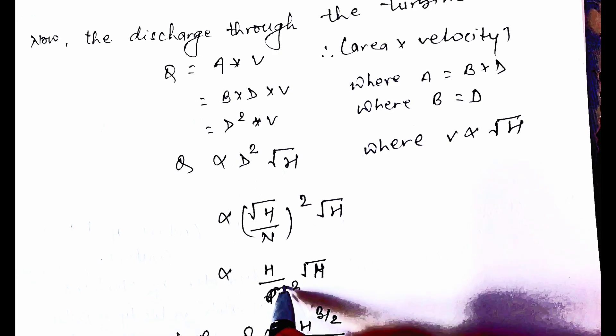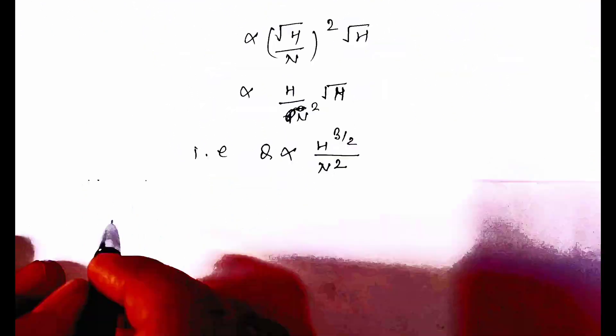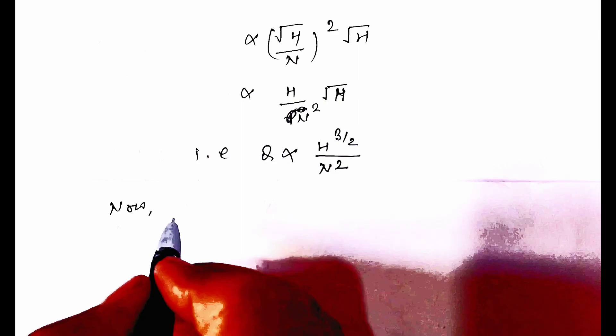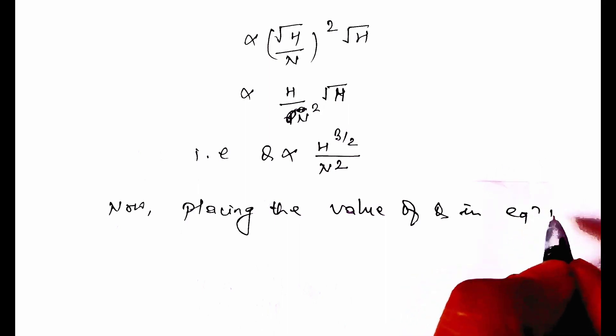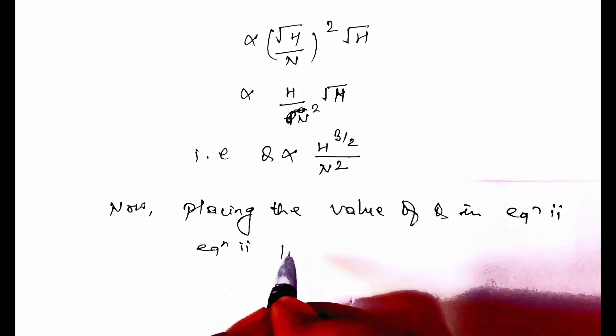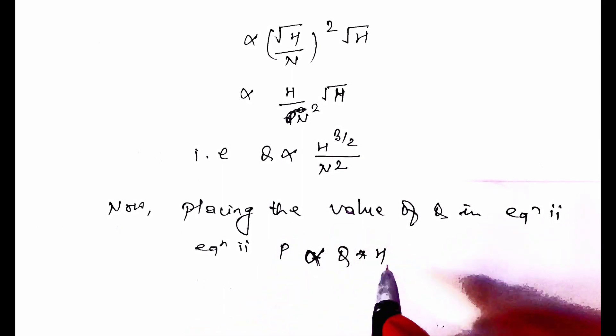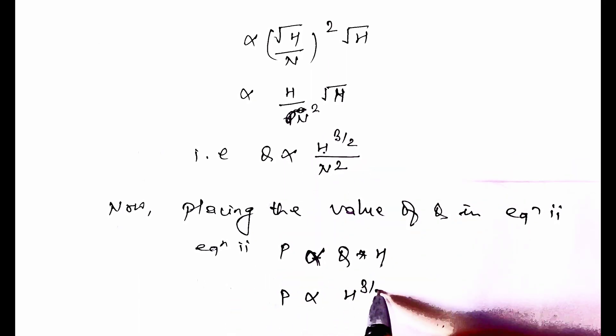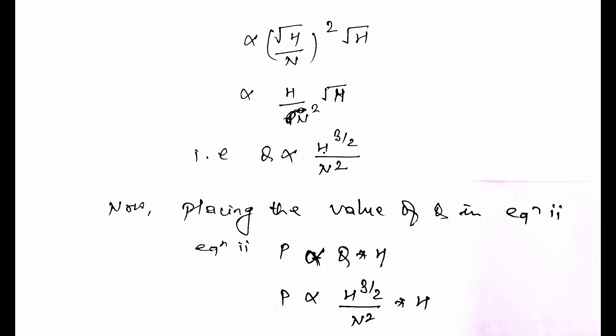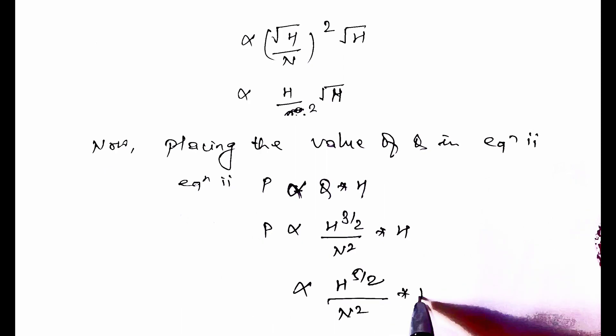Note: there was a correction — the denominator should be N squared, not N. Now placing the value of Q into equation two, where P is proportional to Q times H: P is directly proportional to (H to the 3/2 / N squared) times H, which simplifies to H to the 5/2 divided by N squared.